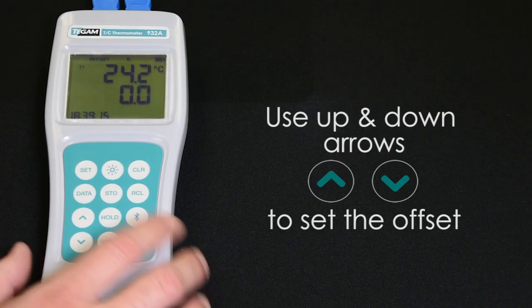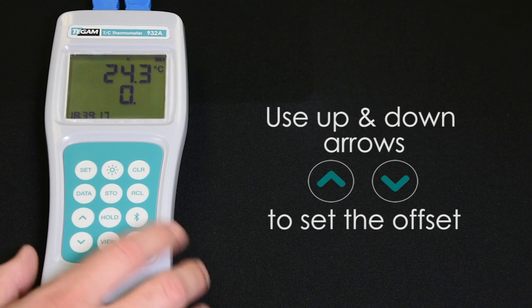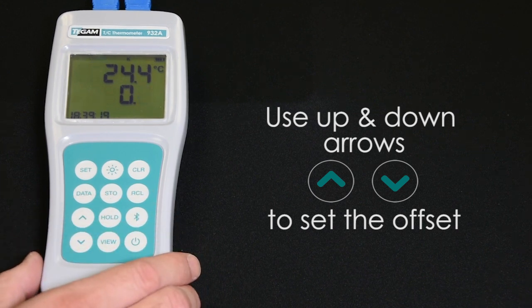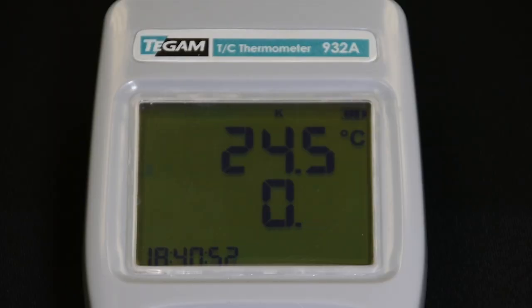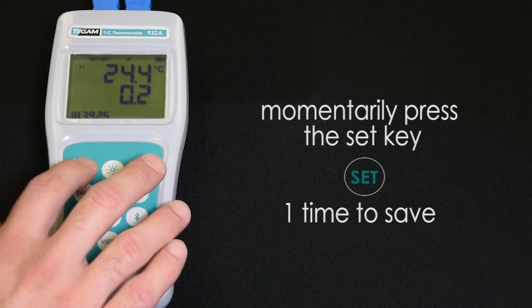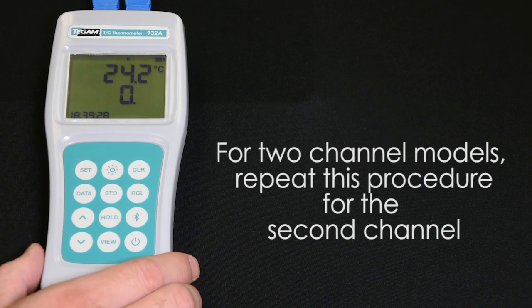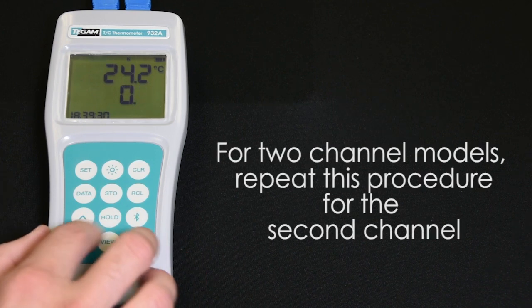Use the arrow keys to set the offset from your existing probe calibration data in 0.1 degree increments. Once the proper value has been set, momentarily press the set key to save that value. For 2-channel models, repeat those steps for channel 2.